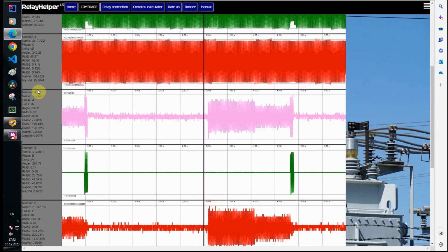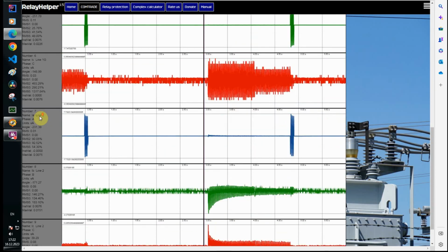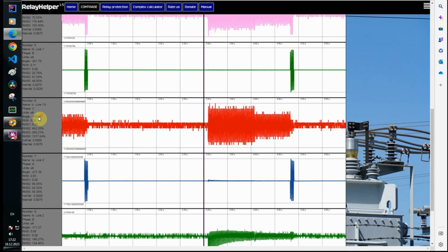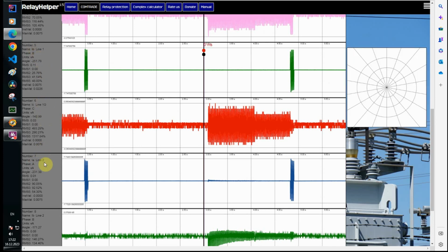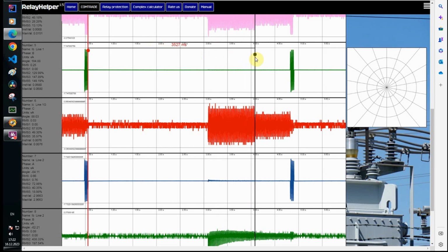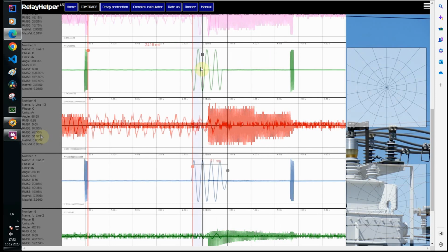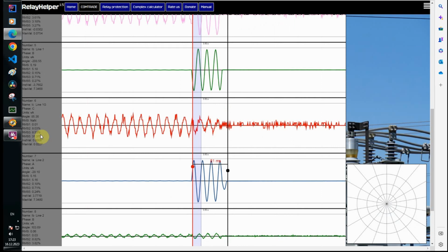I removed the unnecessary channels. Here, there is only the voltage of the bus and the currents of 2 lines. On the first line, phase B is damaged, on the second, phase A. Here we see a trip from the side of substation A, here a reclose from the side of substation A, here a reclose from the side of substation B, and then a short circuit occurs again. Let's take a closer look. At substation A, the first line trip was a little earlier, with an approximate time of about 80 milliseconds.